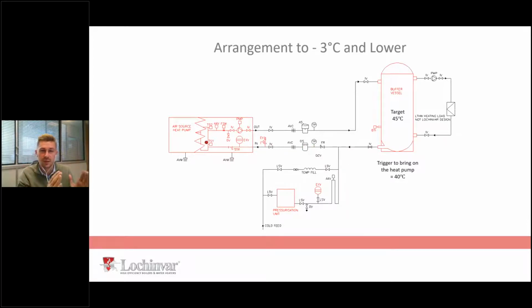And the impact of that is if you've got a 50 kilowatt air source heat pump or a 50 kilowatt boiler, the boiler is probably going to be working like 70-50, so 20 degree delta T. So for the same input with that larger delta T, it means you've got a quarter of the flow rate. So if you're a mechanical engineer who's used to working with boilers, just bear in mind that when you come onto your air source heat pump size, the flow rates will be significantly higher. A quarter of the delta T does typically mean 4 times the flow rate. So 4 times the flow rate means an increased water velocity. And if you've got an increased water velocity, what you've probably got is an increased pipework diameter to make sure you're not going to get sound resonating through the pipes and scrubbing occurring in the copper, things like that. So 5 degree delta T on the air source heat pump, just bear that in mind. A little twist away from what we're used to if we work with traditional heating systems, but it's just worth mentioning. And then your secondary side of the system works independently, and it'll just be happy that it's got a thermal store sat there, a buffer vessel at a design set point of say 45 that it can take off and send to our various zones.